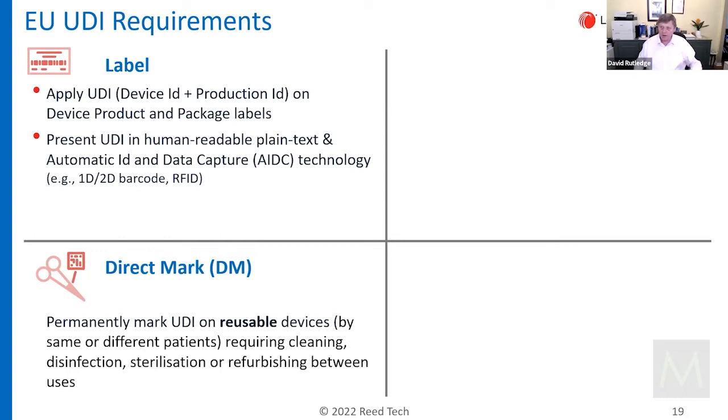I'll wait till someone else talks, because there's also the problem that on your devices, you don't have enough room to put all the information on. Yep. So you're going to make a choice. What do I put on? And as a manufacturer, you think traceability is paramount. So if you can identify the manufacturer, and if you can identify the serial number or anything like that with a UDI, then that's the minimum.